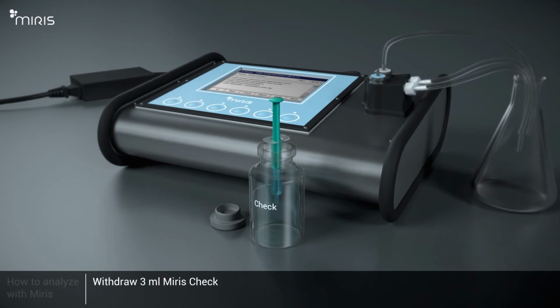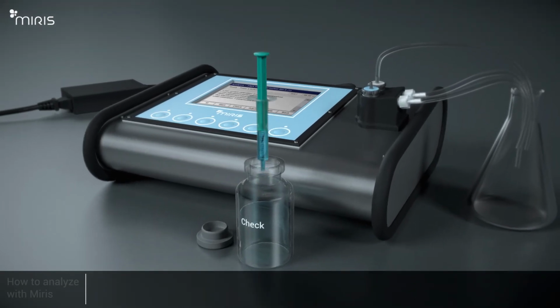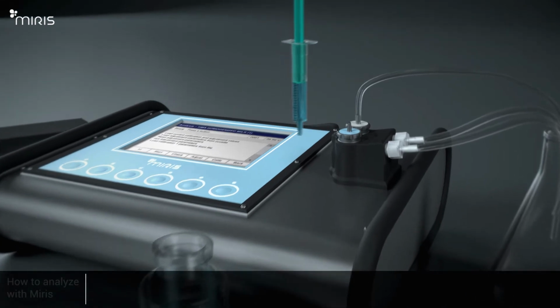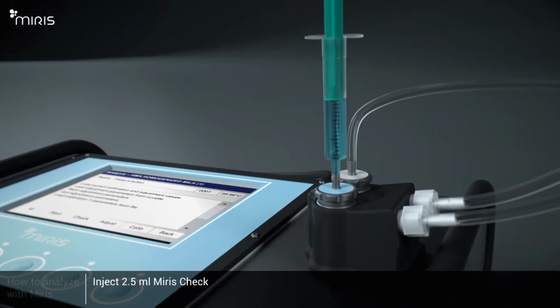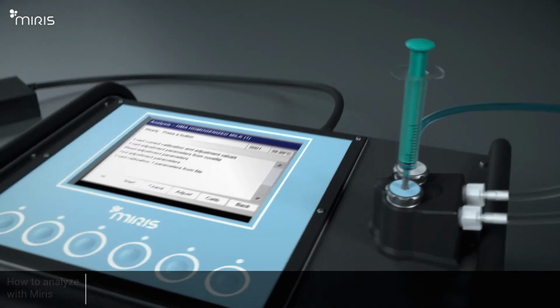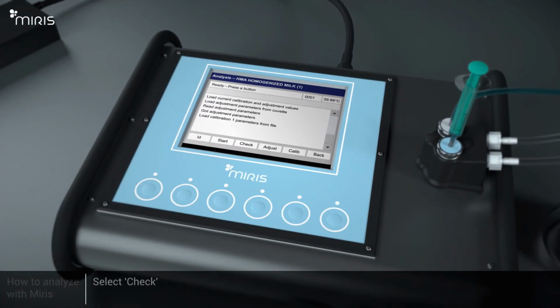Withdraw 3 milliliters pre-warmed Miris Check solution. Inject 2.5 milliliters Miris Check solution and leave about 0.5 milliliters in the syringe. Leave the syringe on the inlet. Select Check to begin the zero setting of the Miris HMA. Wait approximately 60 seconds.